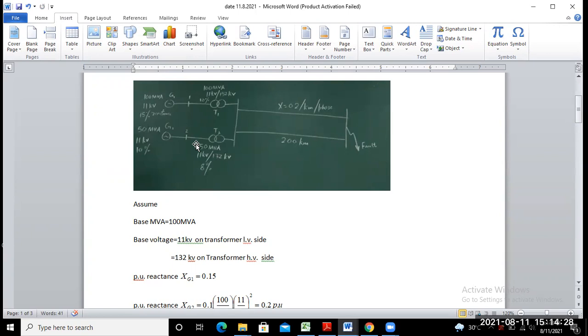Now, what is our next step to find the fault current? The next step is to draw the single line reactance diagram of the power system. Whatever components exist in this system, we represent them by their reactance value in the single line diagram. The generator is always represented by its induced EMF and its per unit reactance, as calculated for generator 1 and generator 2. These two are in parallel through transmission, transformer 1 and transformer 2.